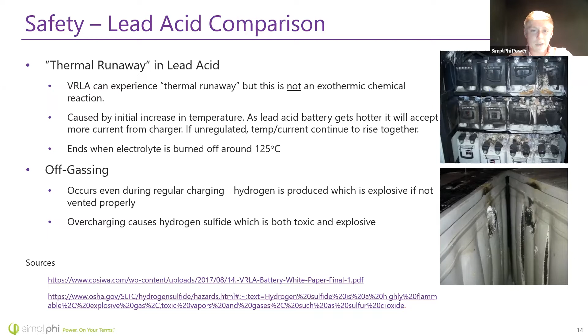You may be thinking 125 degrees Celsius isn't going to start a fire. However, during this thermal runaway event with lead acid, there is off-gassing of hydrogen sulfide, which is not only toxic but very explosive and flammable. We've heard of and seen explosions with lead acid batteries that weren't properly ventilated. This off-gassing occurs somewhat even during regular charging, hydrogen is produced during standard charging of a lead acid battery, which is why you need ventilation, because if the hydrogen isn't vented, it's explosive.